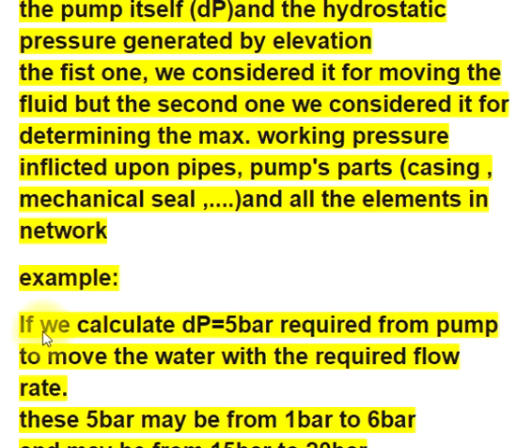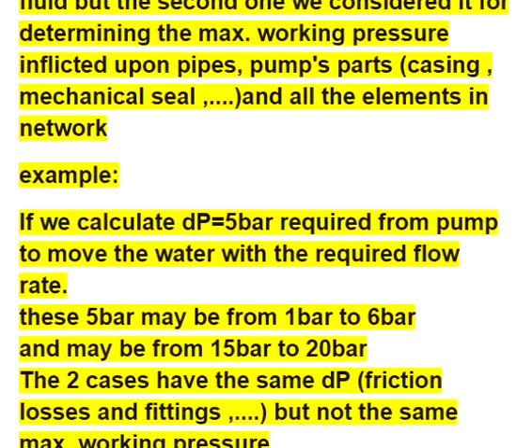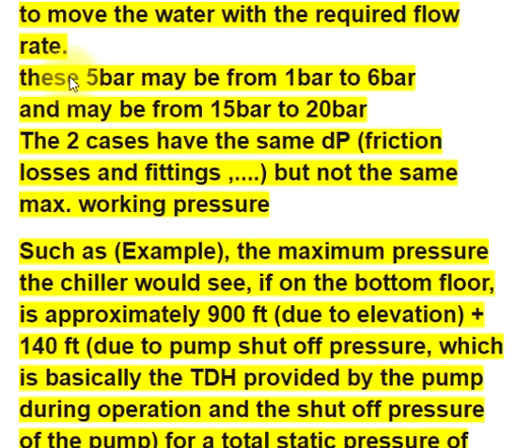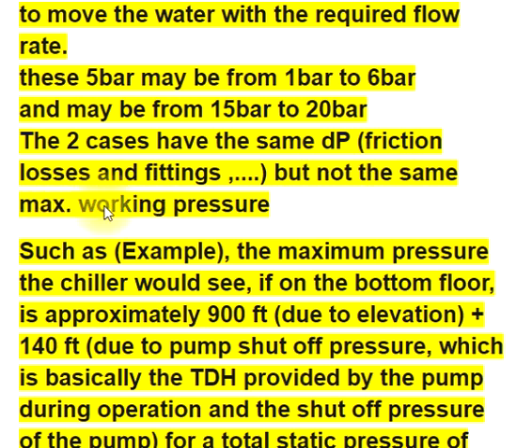For example, if we calculate DP equals 5 bar required from the pump to move water at the required flow rate, these 5 bar may range from 1 bar to 6 bar, and may range from 15 bar to 20 bar. The two cases have the same DP, friction losses, and fittings, but not the same maximum working pressure.